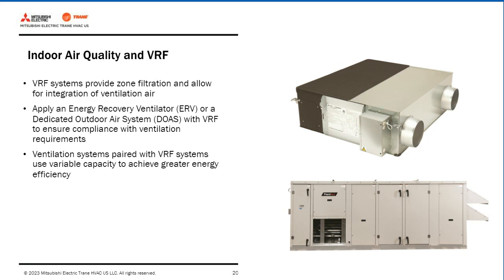In more humid climates like we have here in the South Texas market, we use dedicated outside air systems quite a bit, and that tends to be a better solution for our climate. The dedicated outside air system can condition up to 100% of the ventilation air load and can offset humidity from the outdoor air. It can also deliver dry air to offset moisture already within the building. With the DOAS, outdoor air enters through one side of a rotating heat exchanger while exhaust passes through the other side when we utilize ERVs.